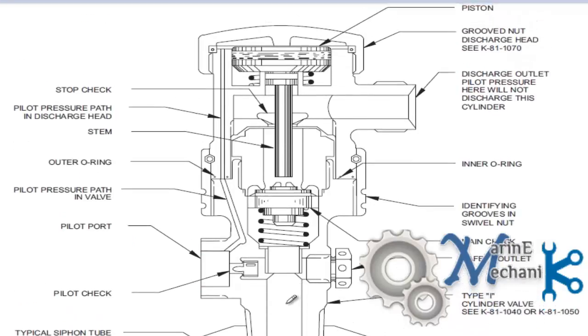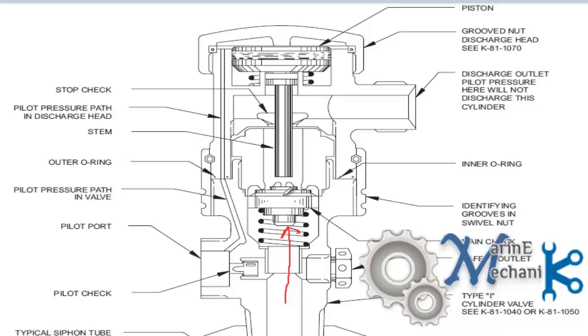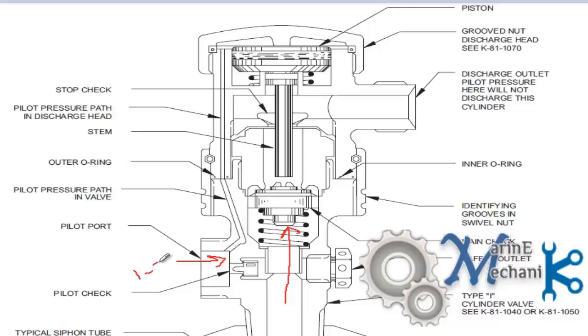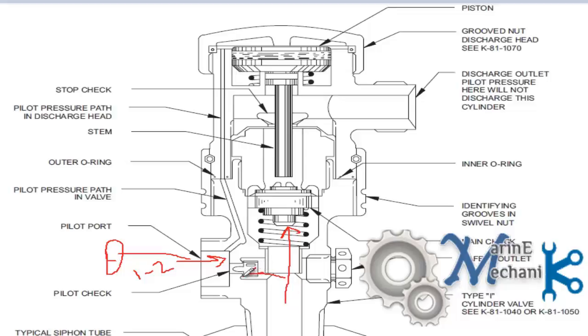You know the bottle pressure, the CO2 comes here along with the spring force keeps this valve closed. Now, you are operating CO2 pilot bottle. The CO2 comes here. Now, this pilot check valve cannot be opened by the lower pressure CO2 from the pilot bottle. The 1 or 2 kg CO2 from the small pilot bottle cannot open this pilot check valve. The reason is the CO2 inside the main bottle is more pressure. So the back pressure is more. It cannot open now.